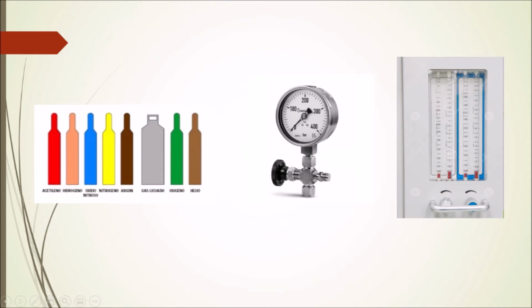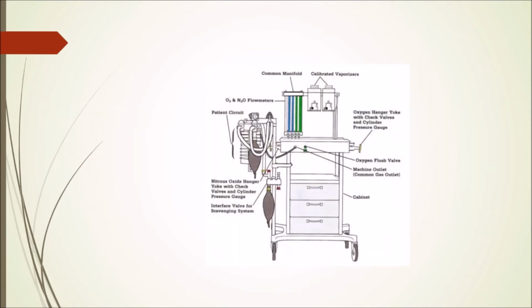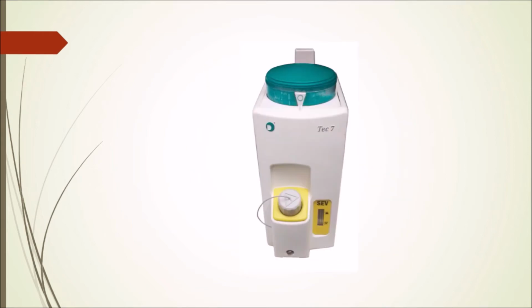The nitrous oxide and the oxygen flow controls are interconnected in such a way that the proportion of oxygen in nitrous oxide can never fall below a minimal value, to prevent a hypoxic breathing mixture. This image shows how the gases are drawn from the hospital gas station and handled by the flow meters and valves. How does the vaporizer work in the anesthesia machine?